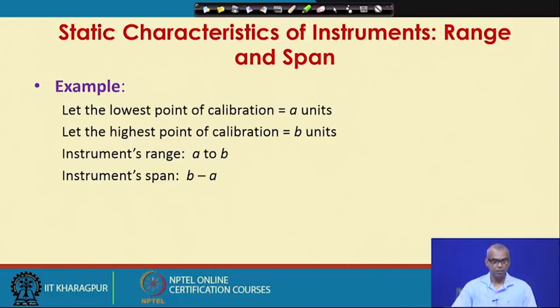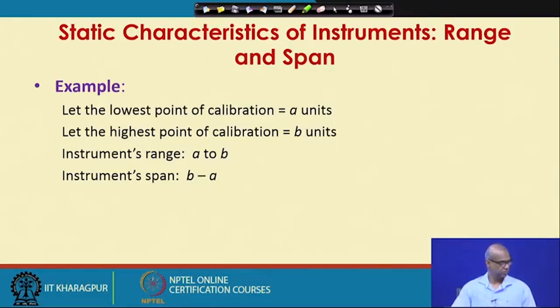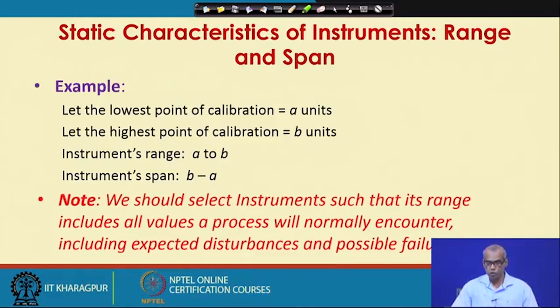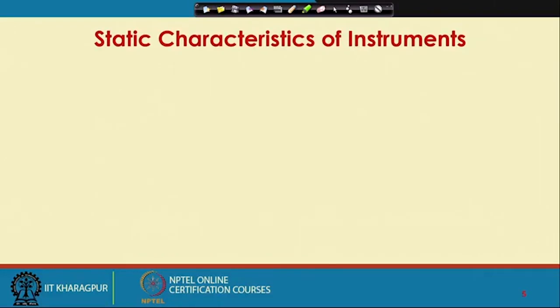Let us take a simple example. Let the lowest point of calibration be A units and the highest point be B units. Then the instrument's range is A to B, whereas the instrument's span is B minus A. We should select instruments such that their range includes all values a process will normally encounter, including expected disturbances and possible failures during measurement.